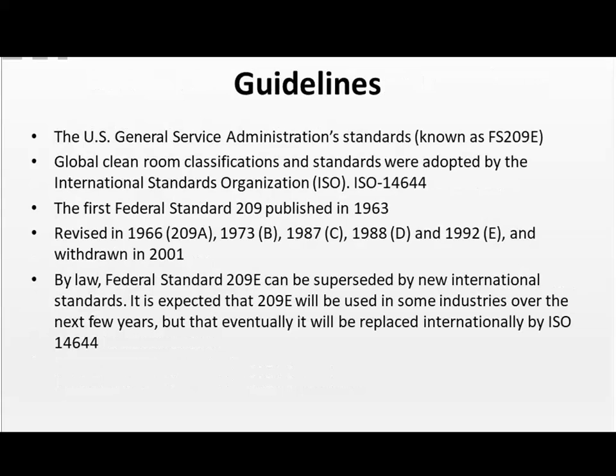The guidelines for environmental monitoring, as we said earlier, are the federal standards, the FDA standards. That document is FS209E, which has now been replaced by the ISO standard, ISO 14644. The federal standard was published in 1963 and revised in 1966. They then withdrew it in 2001, and it has been replaced by the ISO standard 14644.